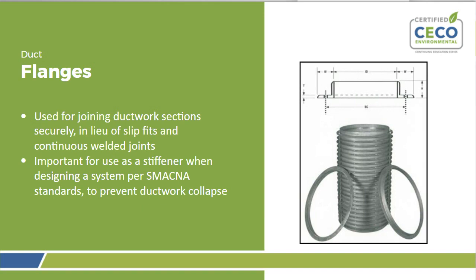An example would be if you have a SMACNA manual, you open it up to, let's say, 6 inches of negative pressure, you pick a 30-inch diameter duct for class 2, and it'll give you different options. You can go with a 12 gauge and not need any stiffeners, or you can go with a 14 gauge and have stiffeners every 20 feet. And again, it's designed so that it doesn't collapse because of the pressure, or the particulate that could build up in it. They've actually calculated those numbers based on as much as 50% buildup of material for a safety factor for you.